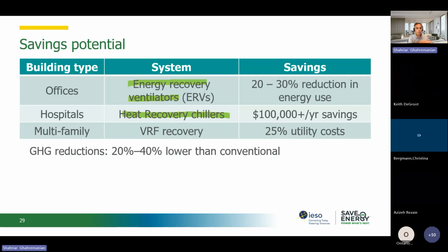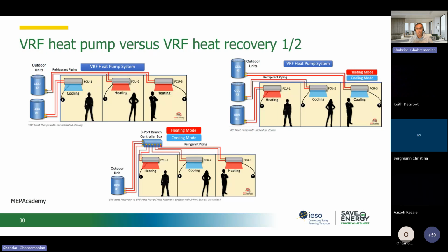The same goes for multi-family residential VRF heat recovery. And on top of energy, which is actual cost reduction for us, there is emission reduction. Emission reduction using any heat recovery is around 20 to 40%. If we use an ERV as an example, with 50,000 CFM, and let's assume the ERV has 60% efficiency with a 2,000 million BTU annual heating load, then the recovery is going to be a lot. This is going to be around $14,000 to $20,000 in fuel saving every year. There are many examples, and we should benefit from them.